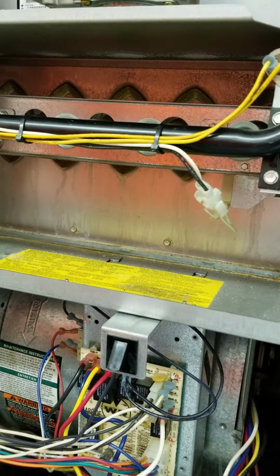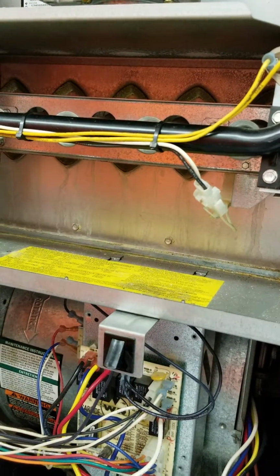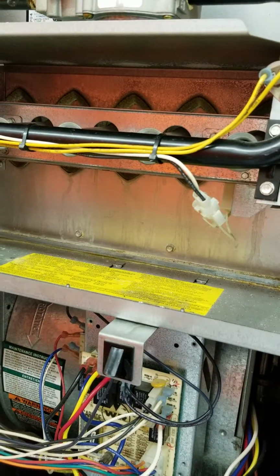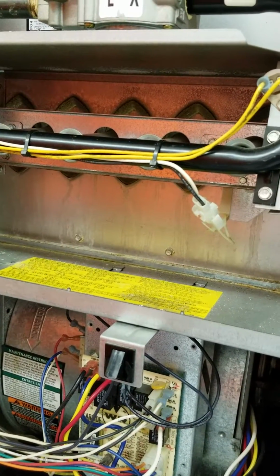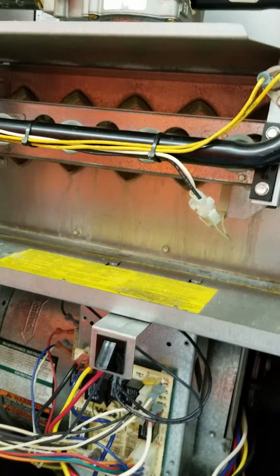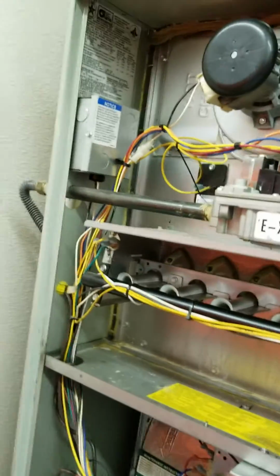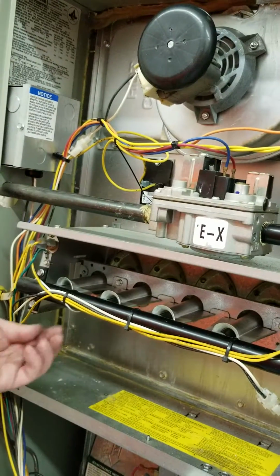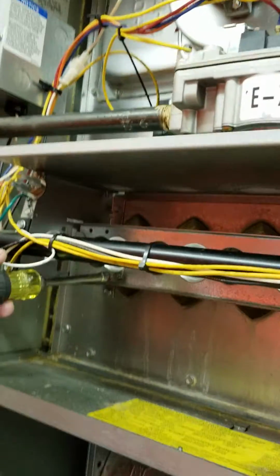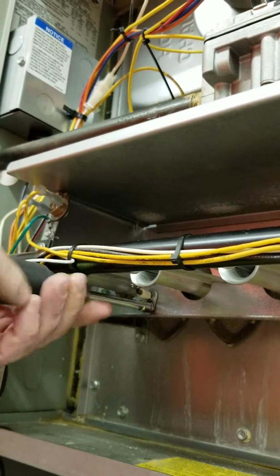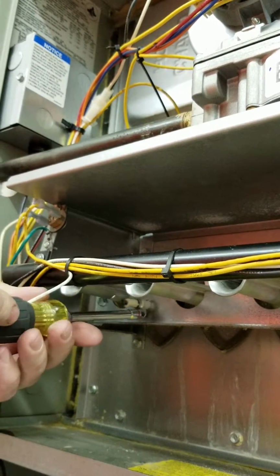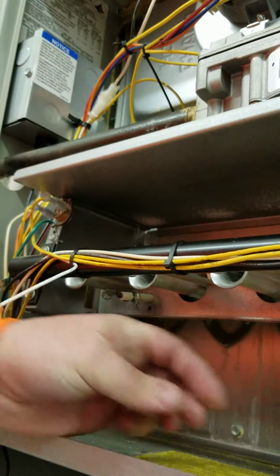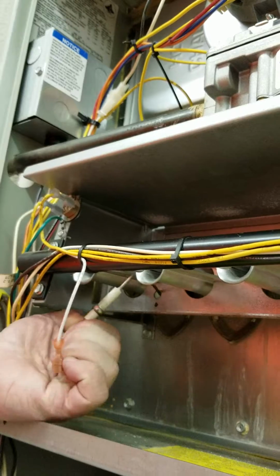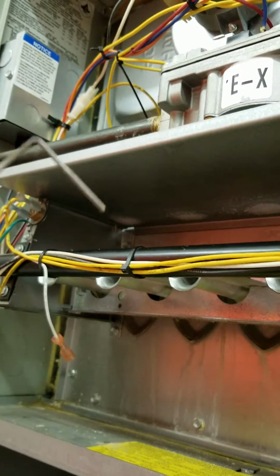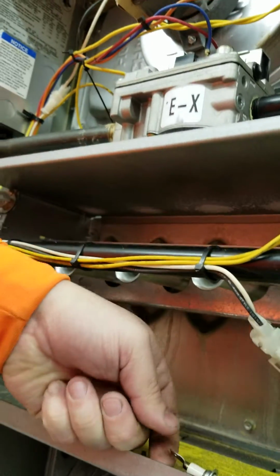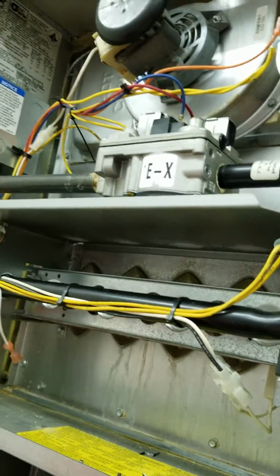If for some reason your furnace does not have one, or it has been bypassed, the next thing you will do is go directly to the circuit breaker panel and turn off the power to the furnace. Hopefully it's labeled. Okay, so whenever you're ready, Damien, next step would be to remove the sensor rod, which is right there. Be careful to save your screws. And you can see there, that's what that rod looks like. They're not always bent. Some of them are straight. Depends on the model of furnace and the brand.